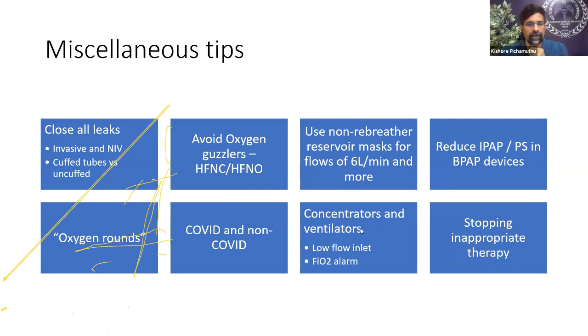The other issue with concentrators and ventilators is the FiO2 alarm. You must have ventilators where you're able to suppress the low FiO2 alarm, because oxygen that's coming from concentrators is often not 100%. So that is sensed by the ventilator, and then it starts alarming, saying that the oxygen supply is not pure 100% oxygen, and that can be a big nuisance. Some ventilators will even start shutting down after some time. So there should be a way to suppress this alarm.